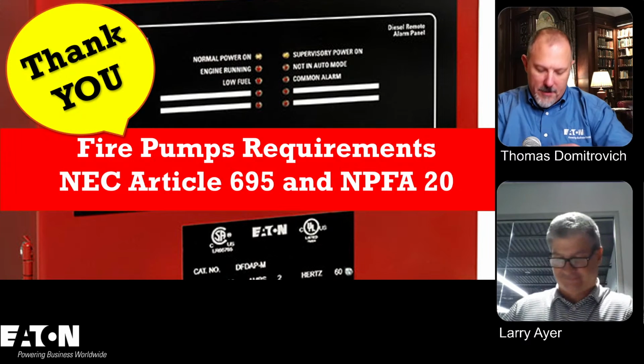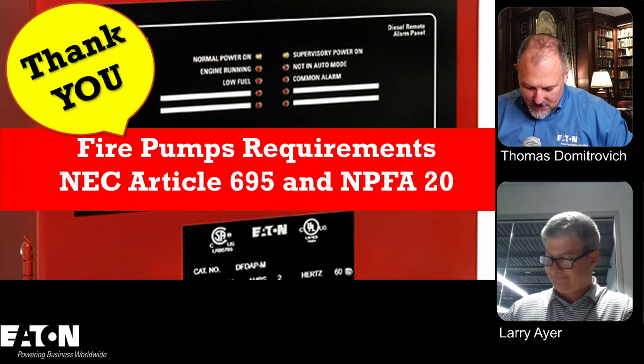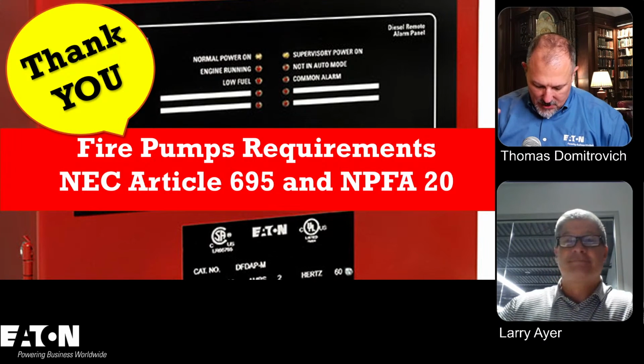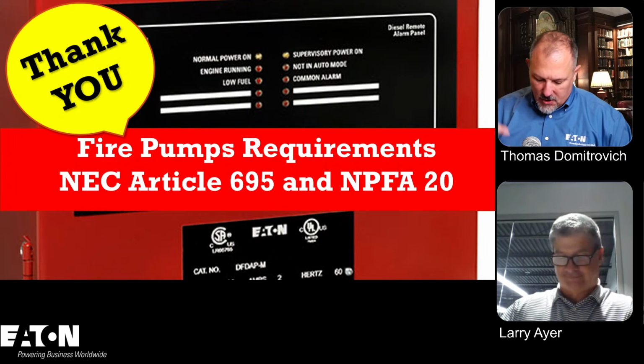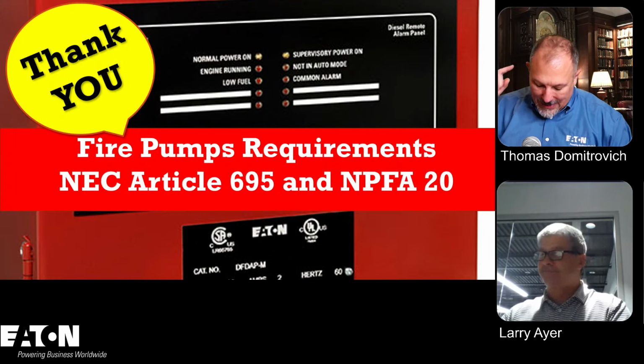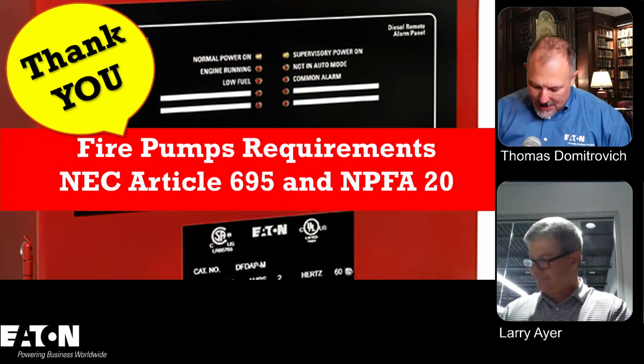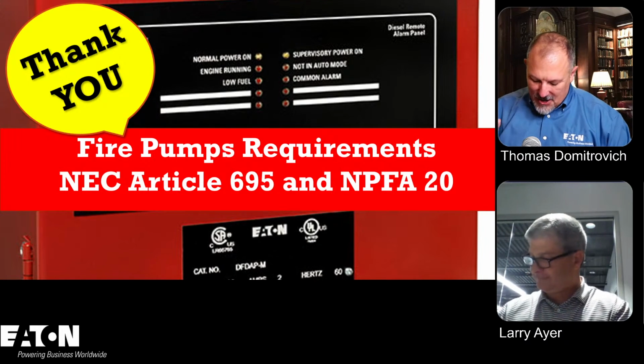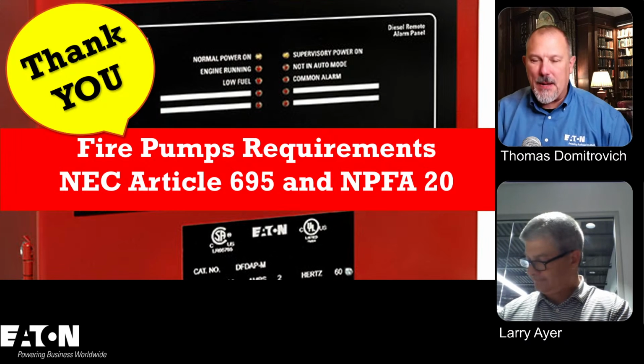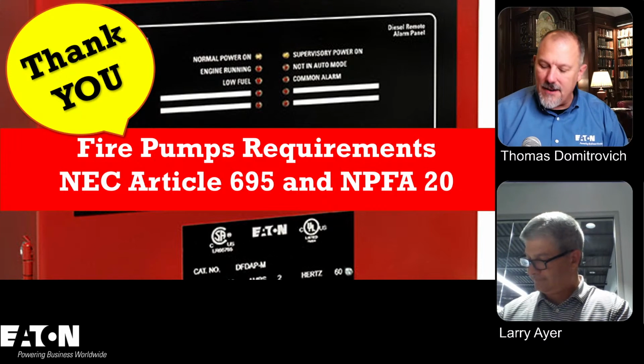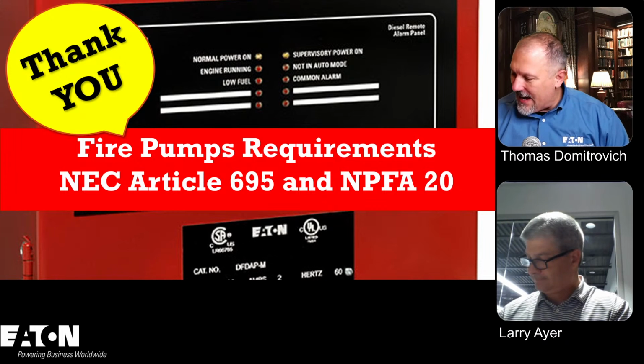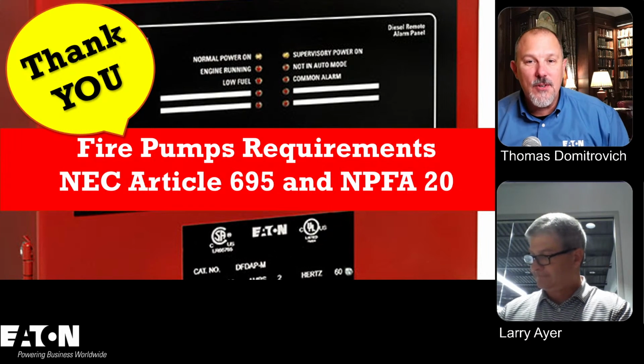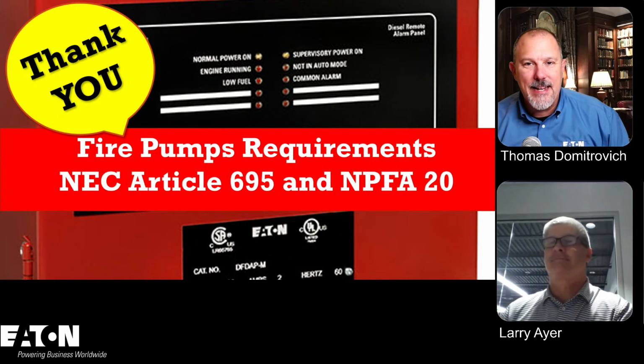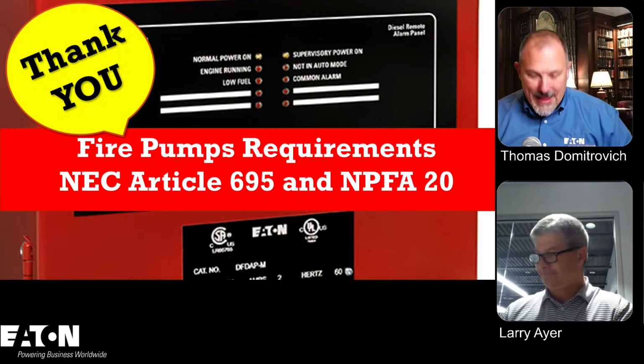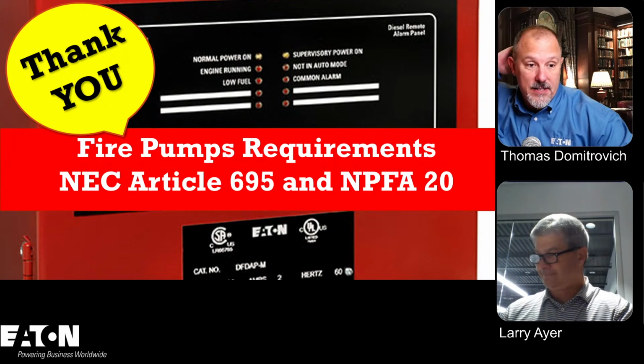It's been 2 hours. So, number of disconnecting means: a single disconnecting means and associated overcurrent protective device shall be permitted to be installed between the fire pump and one of the following: a listed fire pump controller, a listed fire pump power transfer switch, a listed combination fire pump controller and power transfer switch. It is in there, and we found it. We told Jeff Fecteau, I look forward to your public input, and he got it done. Now that's speed. Thank you, Felix, for finding that.